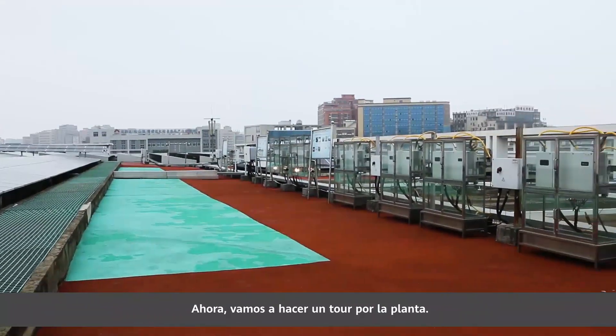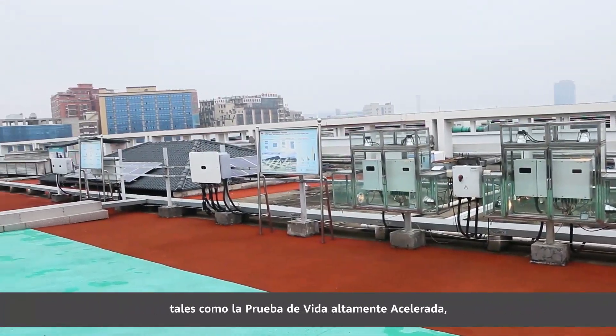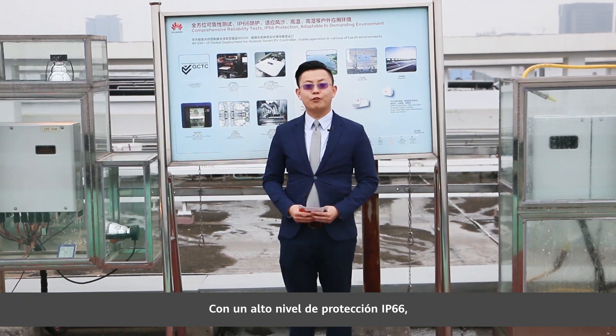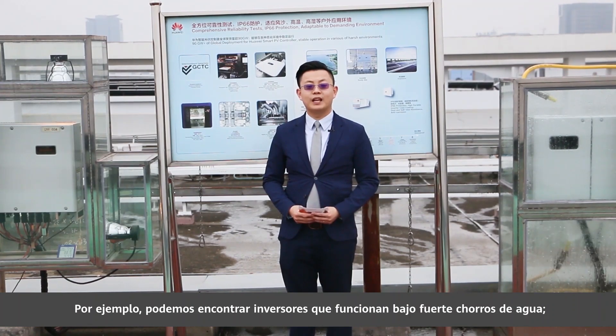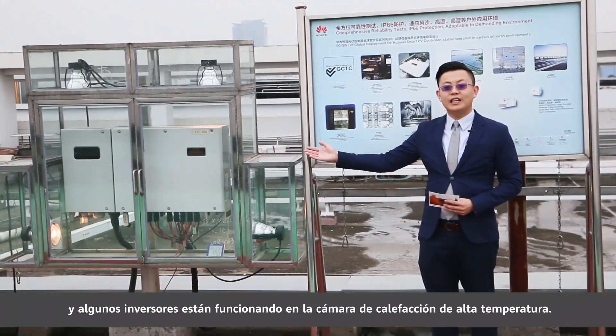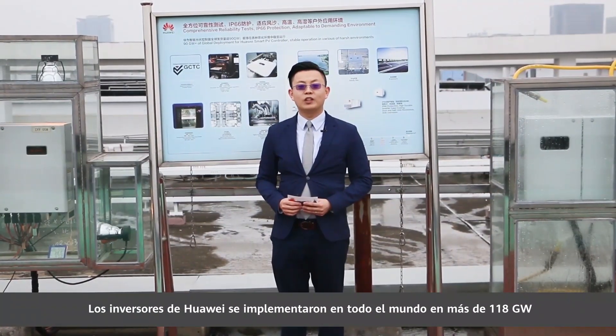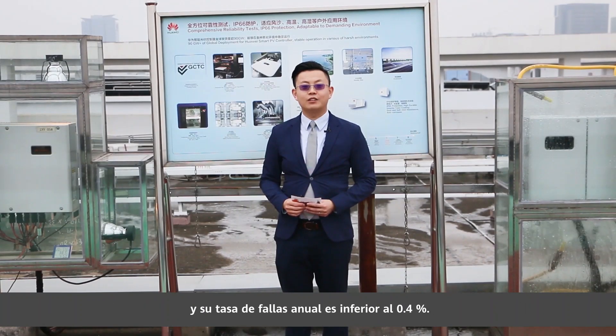Let's have a tour of the plant together. Huawei's string inverter passed comprehensive reliability tests like highly accelerated life tests and temperature humidity bias tests. With IP66 high protection level, the inverter can operate stably in various harsh environments. Here we can see inverters running under heavy water jets, and some inverters are running in a high temperature heating chamber. Huawei inverters were deployed over 118GW globally and its annual failure rate is less than 0.4%.